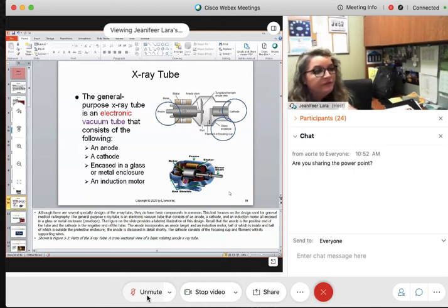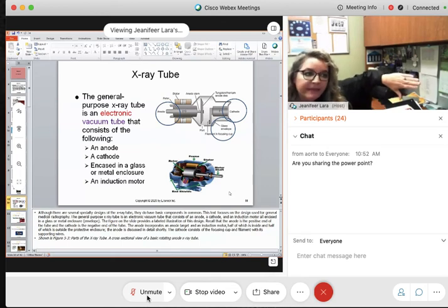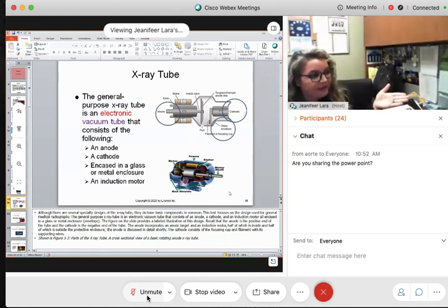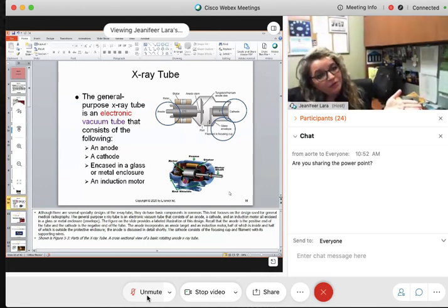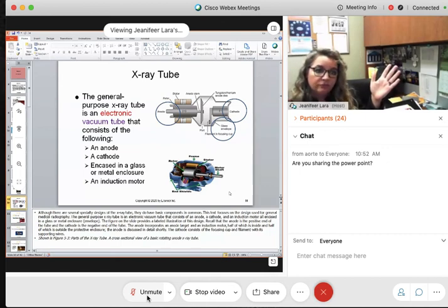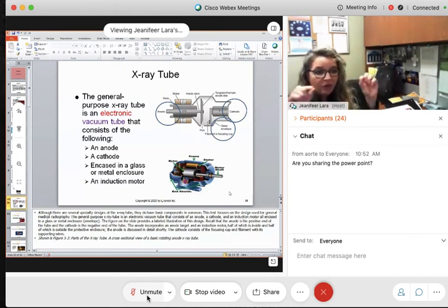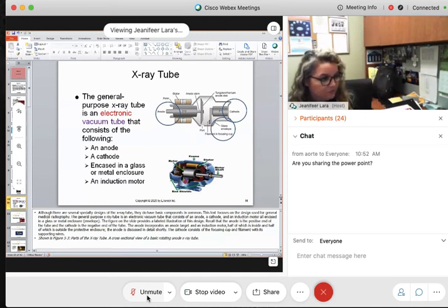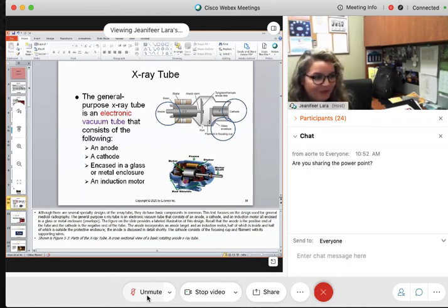Here is the general construct of the x-ray tube. We've already talked about protective housing. Now we're on the x-ray tube. The x-ray tube is a diode — it has an anode and a cathode. Electricity is going to flow. It is empty space — there is a vacuum, no air inside. It can either be constructed of glass or metal.